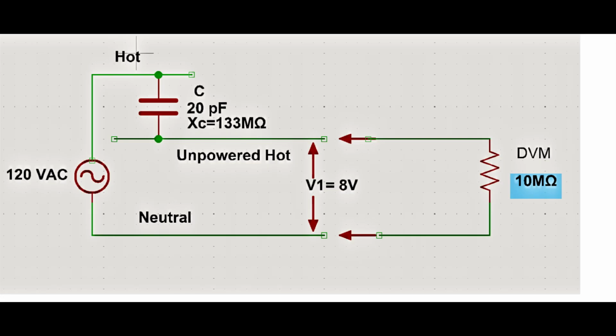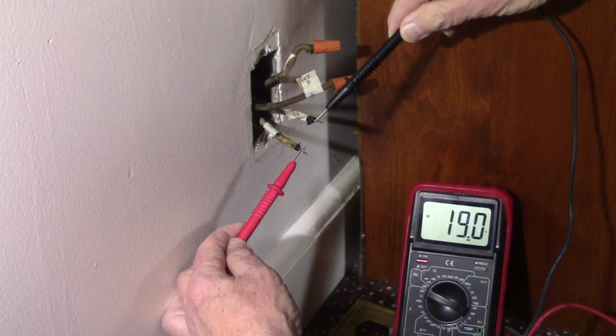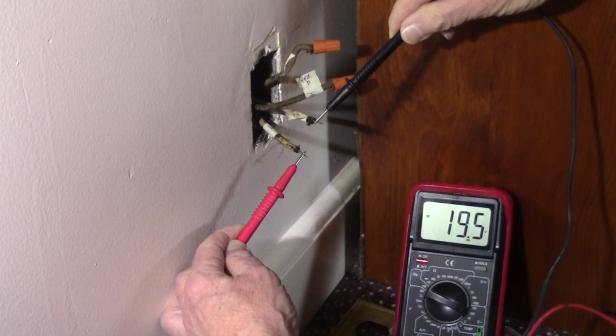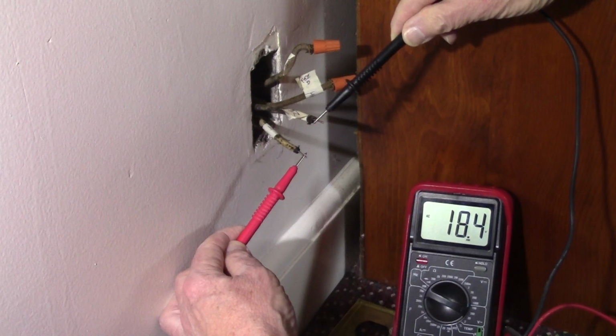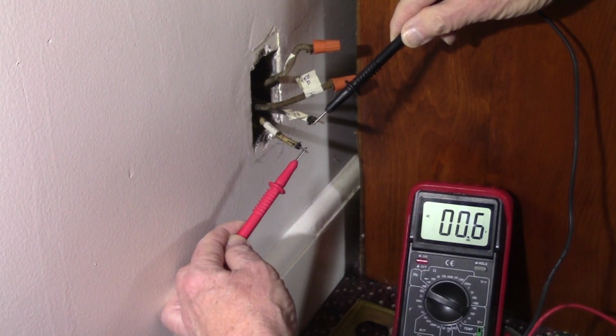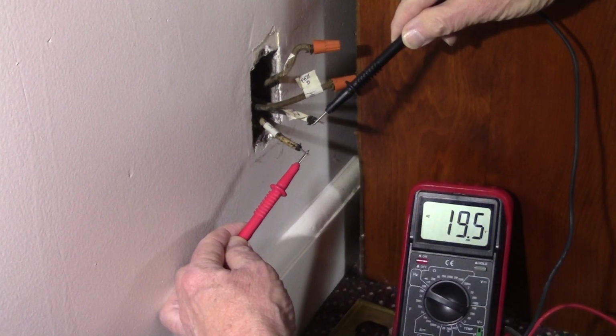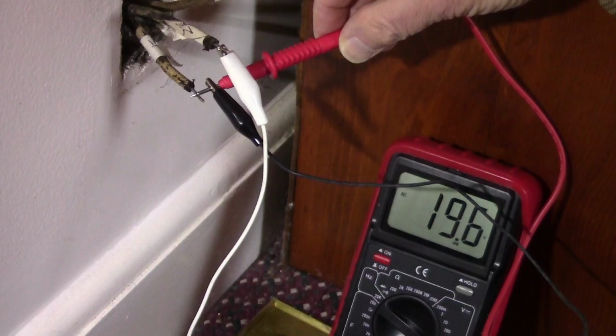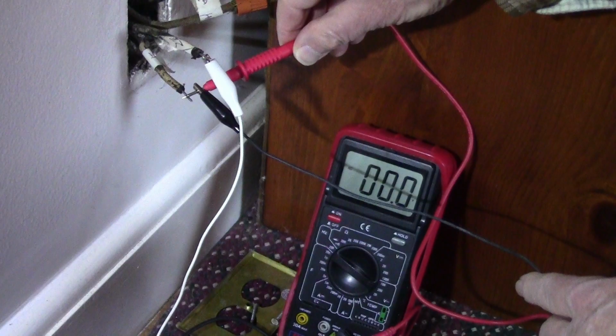If you're wondering why the phantom voltage here is shown as 8 and 19.5 in the actual real-world measurement, the answer is that the former is a calculation based on an educated guess for the value of the stray capacitance as well as the input resistance of the DVM. The actual values are, of course, not exactly the same as this. That means that the measured voltage will not be exactly the same. Also remember that adding the low resistance of the nightlight drops the divider circuit voltage to zero. That's how you can be sure the voltage is what they call a phantom.